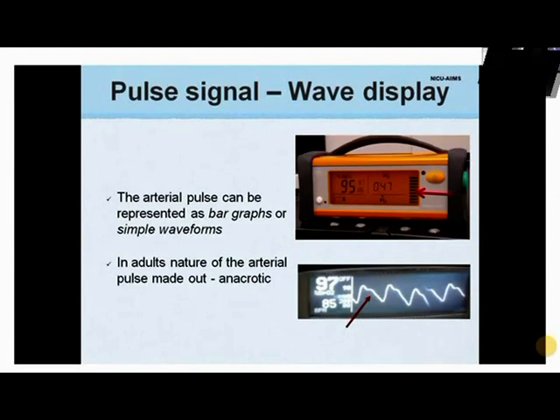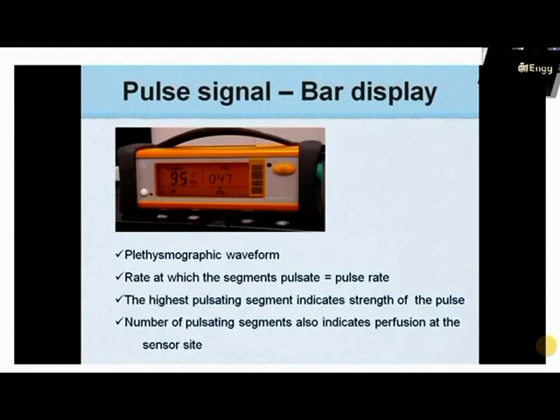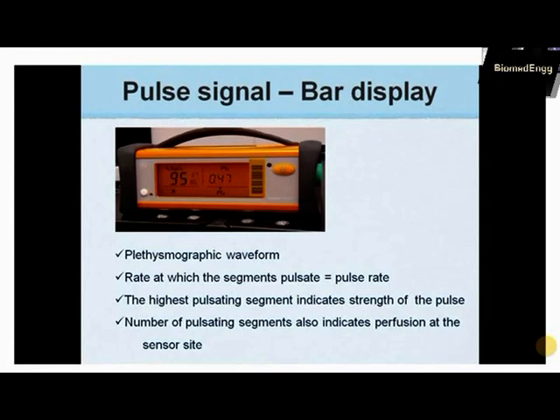In adults, the nature of the arterial pulse can easily be discerned, which is usually anacrotic with a clear notch. When the pulse is presented as bar graphs, the rate at which the segments pulsate is equal to the pulse rate. The highest pulsating segment indicates the strength of the pulse, and the number of pulsating segments indicates perfusion at the sensor site — the more the segments, the stronger the perfusion.